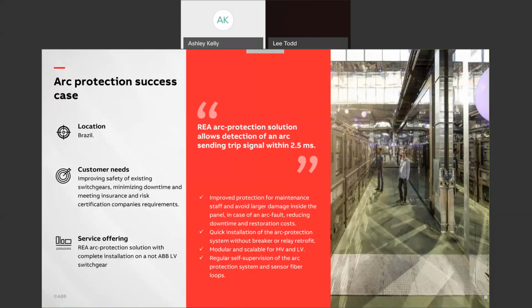The service team locally in Brazil met this challenge and upgraded the protection and control system to the Relion REA arc protection solution. This upgrade was completed on non-ABB low voltage equipment. This REA solution provides protection, detection of an arc, and sends a trip signal to the breaker within 2.5 milliseconds. So extremely fast acting to protect both the operator and protect damage to the equipment.